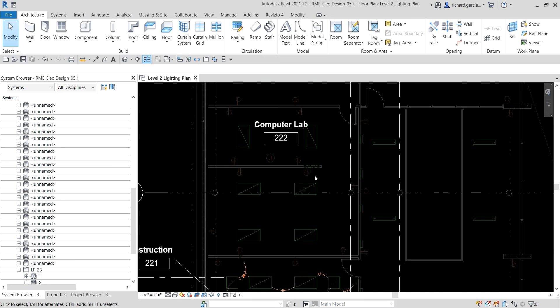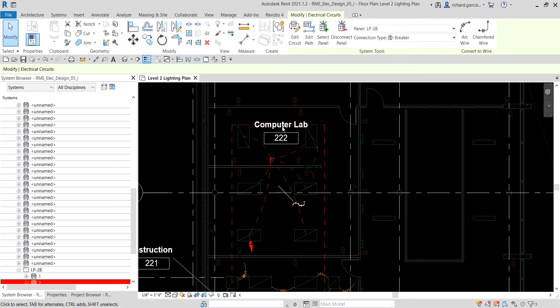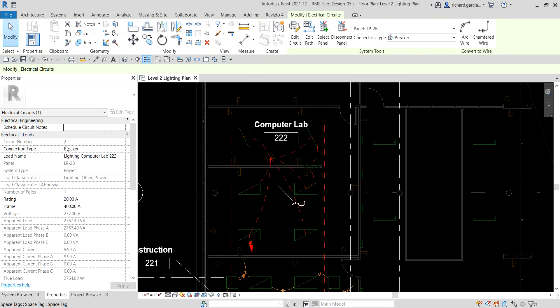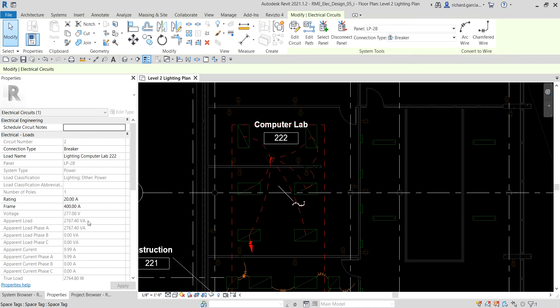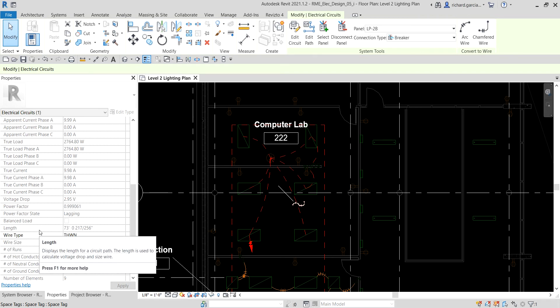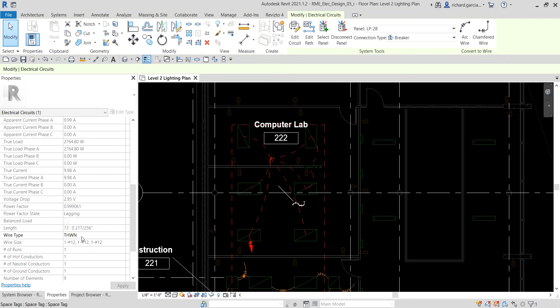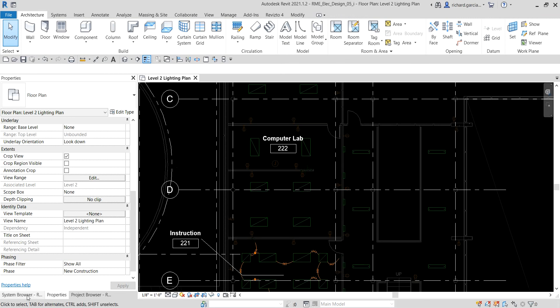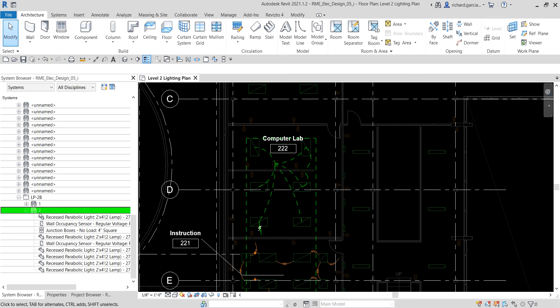If I hover my pointer over one of the sensors and press Tab, then click, it highlights circuit number two. Checking the properties, it confirms this is circuit number two — showing the connection type, the load name, the length of the wire, the wire type (which you can change if you want), and the wire size. On the system browser, circuit number two shows all the elements on that circuit on LP2B panel.